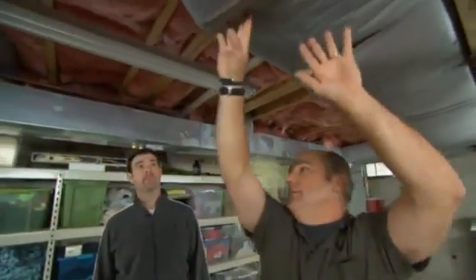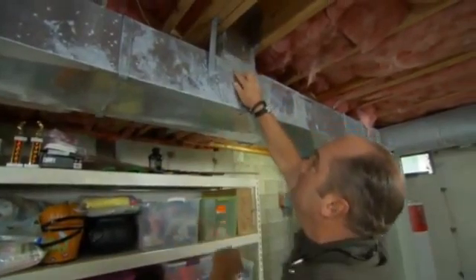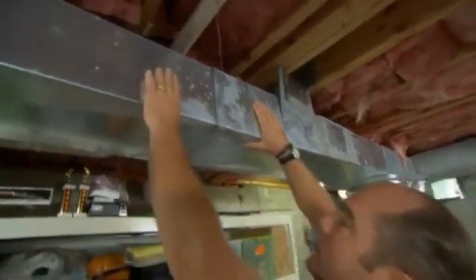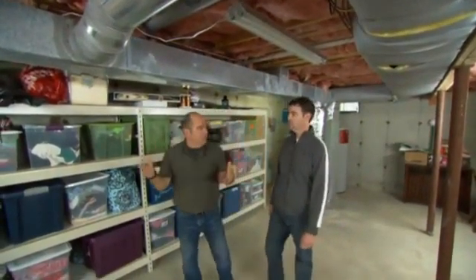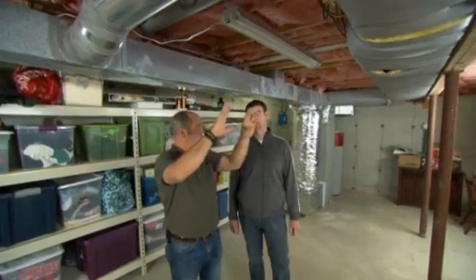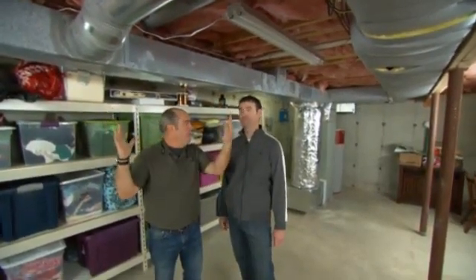This is the supply trunk right here, insulated. But over here you can actually see the real issue with duct work. Here's the return coming from upstairs. When these come together, you can see the installer has sealed this with a mastic — a rubberized cement to seal up the joints, applied with a brush at any place that air could leak out. It's messy, but it's really effective. You also could use a foil tape to seal accessible joints. The challenge: a metal trunk held together only by a metal cleat — that's not airtight. We could try to seal the duct work from the outside, but a great percentage of your duct work is inside the building where we can't get at it.